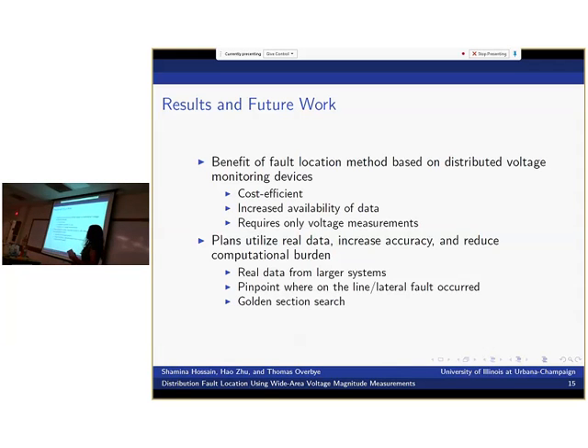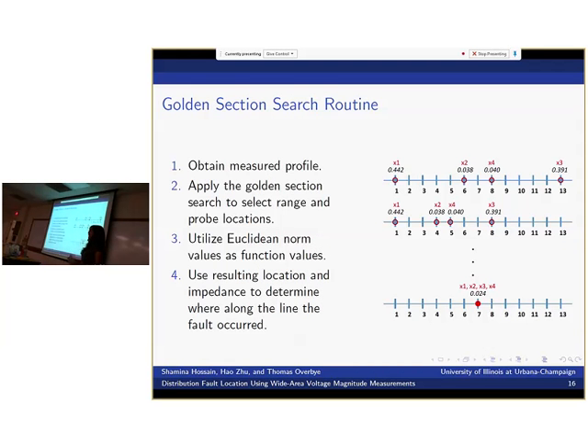And so right now what I'm looking at is using the golden section search routine. The golden section search routine is a technique for finding an extreme minimum or maximum by successively narrowing down a range of values. In our case, after we obtain the measured profile, we can use the golden section search routine to select the range starting and endpoints, as well as the probing locations. And this is selected by using the Euclidean error norm criterion.